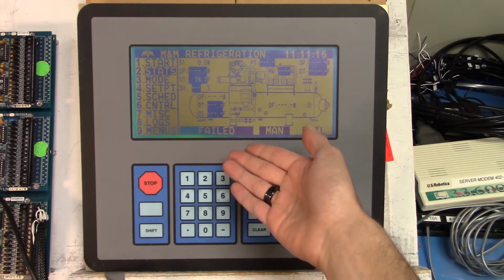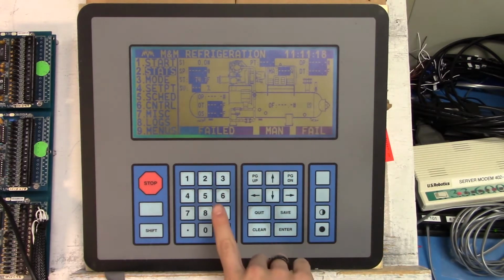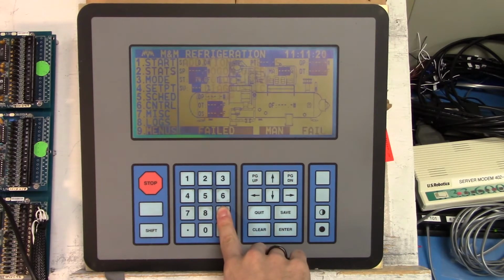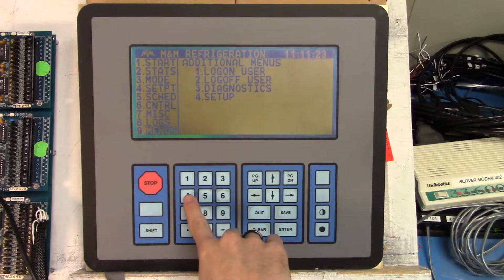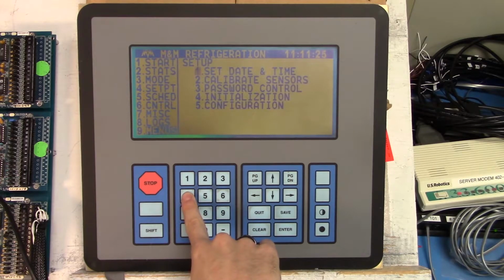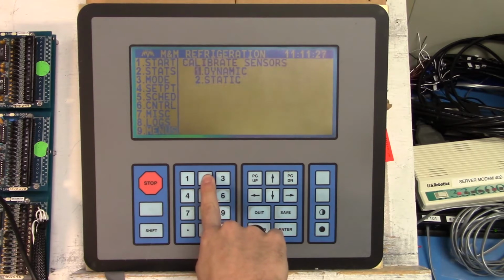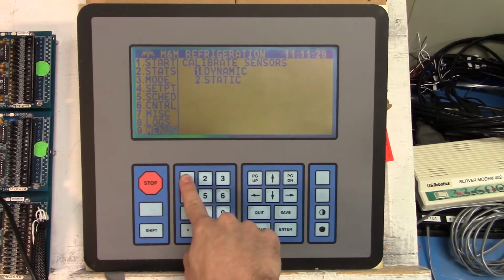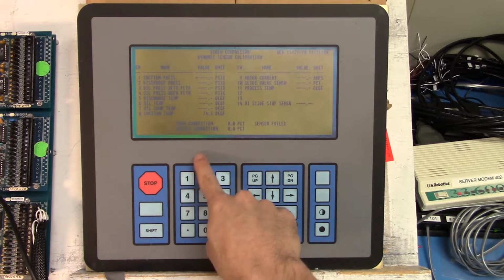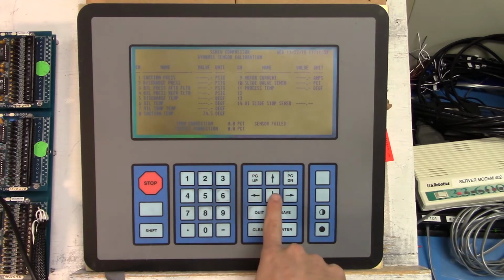While each job is custom made for our clients, the general path for getting the calibration screen is the same. From the main menu, select Setup, Calibrate Sensors, Dynamic, then key down to the sensor being calibrated. In this case, we have a suction temperature sensor on channel 8.